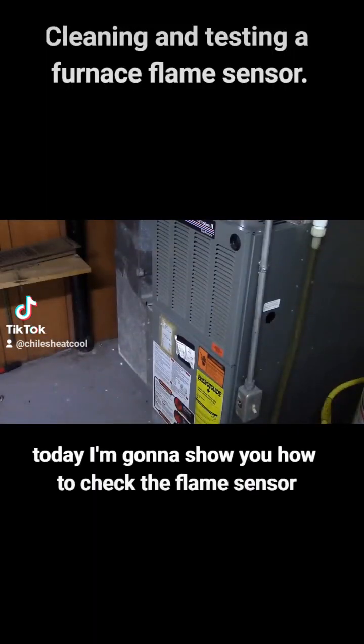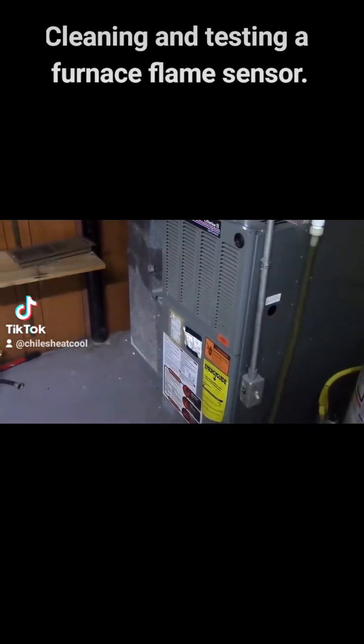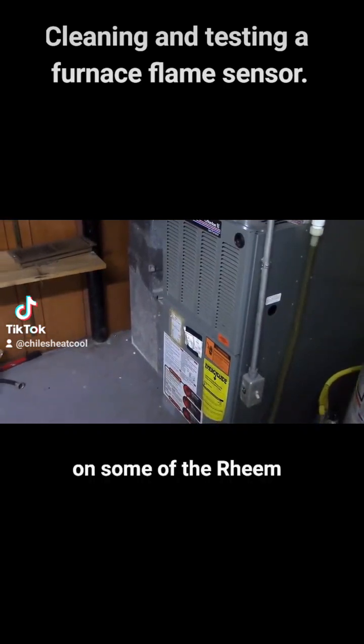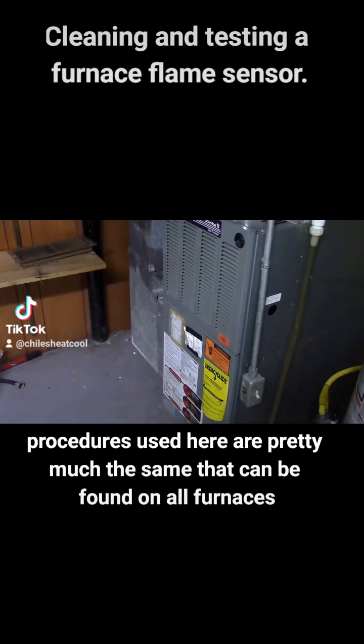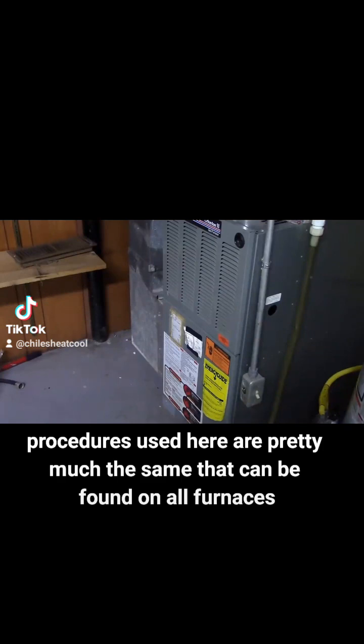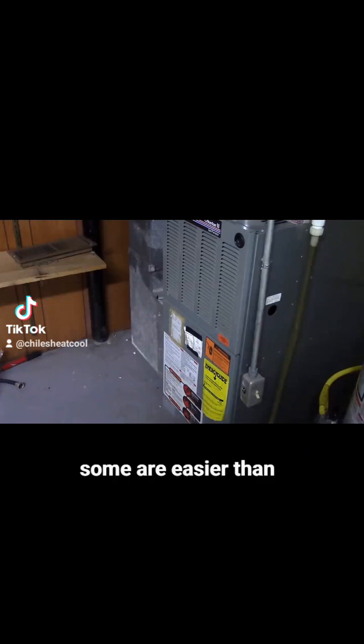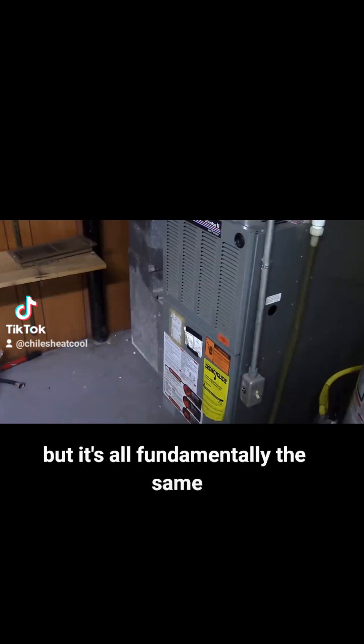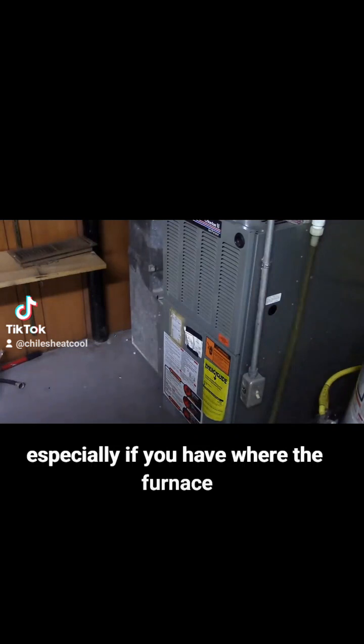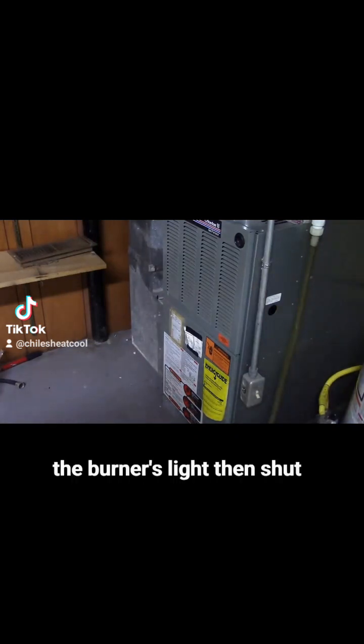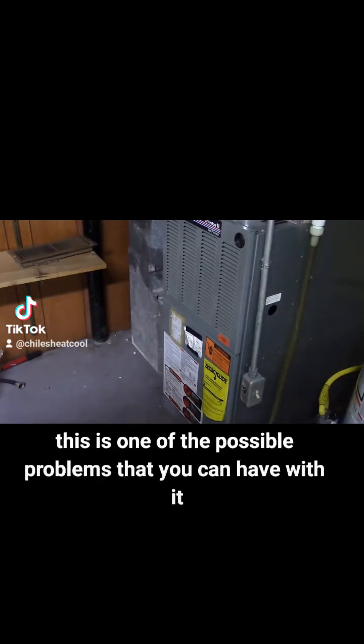Today I'm going to show you how to check a flame sensor on some of the Rheem furnaces. The procedures used here are pretty much the same that can be found on all furnaces. Some are easier than others, but it's all fundamentally the same. Especially if you have where the furnace, the burner's light, then it's shut off. This is one of the possible problems that you can have with it.